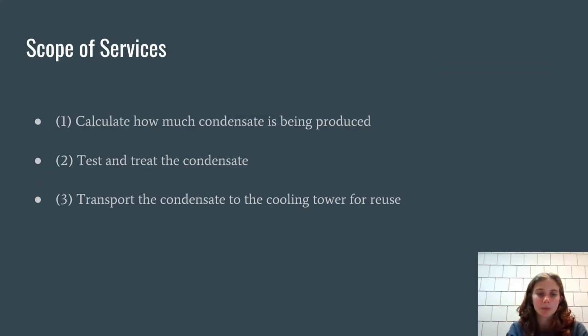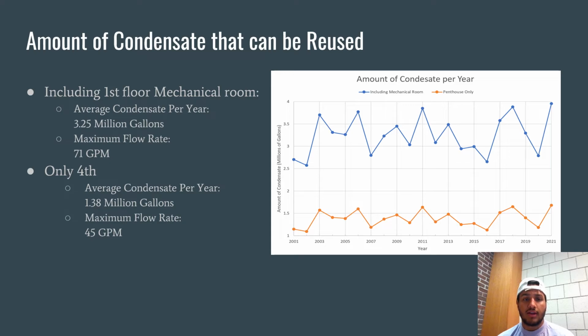The scope of services we will be providing to our client include calculating how much condensate is being produced, testing and treating the condensate, and transporting the condensate to the cooling tower for reuse. We extracted climate data from NASA Power and used a mass rate balance to calculate condensate flow rate. The design that includes the air handling units on the first floor has a potential to save 3.25 million gallons of water per year with a maximum flow rate of 71 gallons per minute. The design that only uses the fourth floor air handling units is projected to save about 1.38 million gallons with a maximum flow rate of 45 gallons per minute. The chart on the right demonstrates the average amount of condensate per year for both designs.